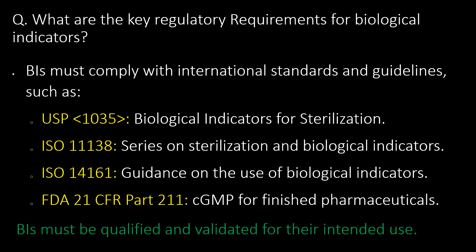What are the key regulatory requirements for biological indicators? Biological indicators must comply with international standards and guidelines such as USP chapter 1035, ISO 11138, ISO 14161, and FDA 21 CFR Part 211. Biological indicators must be qualified and validated for their intended use.